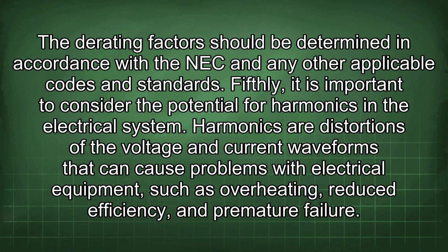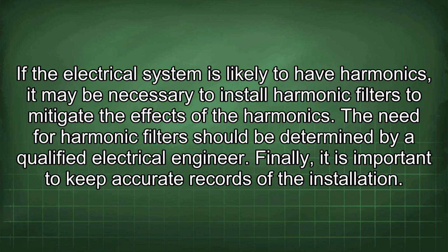Fifthly, it is important to consider the potential for harmonics in the electrical system. Harmonics are distortions of the voltage and current waveforms that can cause problems with electrical equipment, such as overheating, reduced efficiency, and premature failure. If the electrical system is likely to have harmonics, it may be necessary to install harmonic filters to mitigate the effects of the harmonics. The need for harmonic filters should be determined by a qualified electrical engineer.